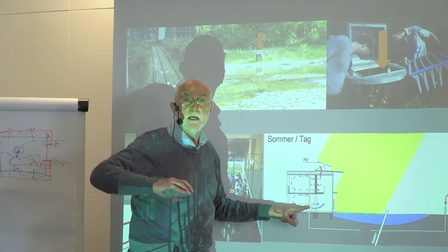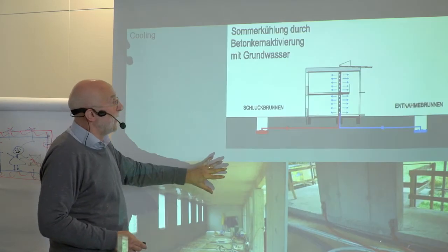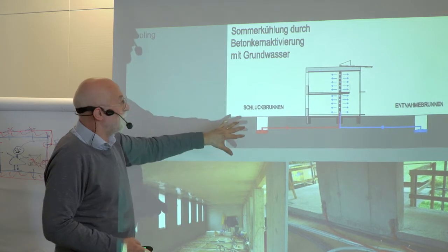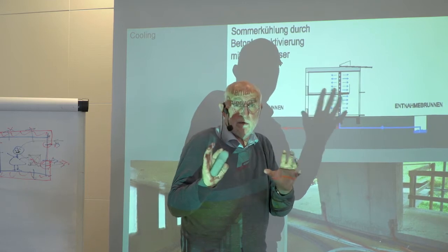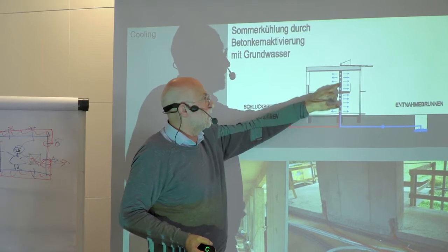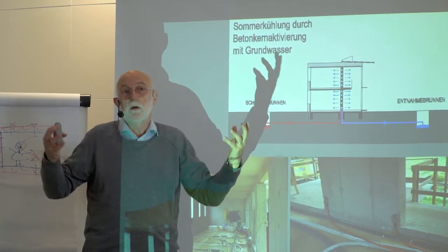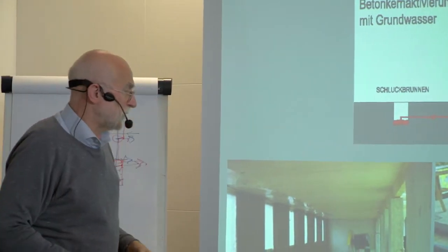is cooled down a little bit and goes into the air exchanger, and it's cooling the fresh air for the people inside. And there is even more: we take the underground water, which is more or less the average outside temperature over the year, might be 15 degrees, and it's cooling down this wall. And together with the other strategies, we are competitive with all these energy-consuming old strategies.